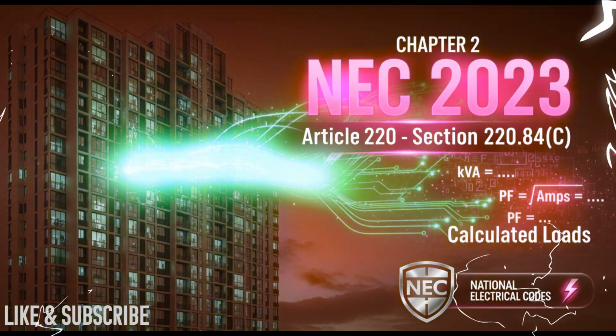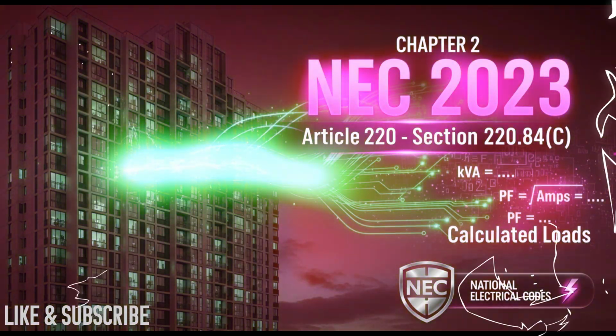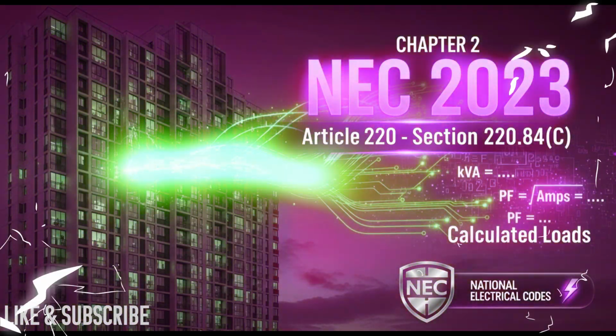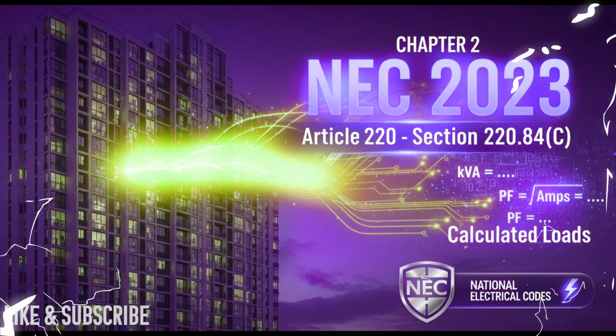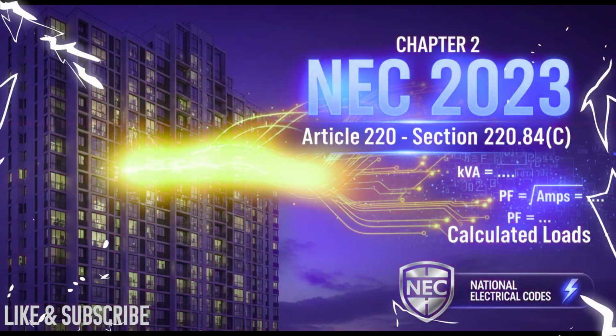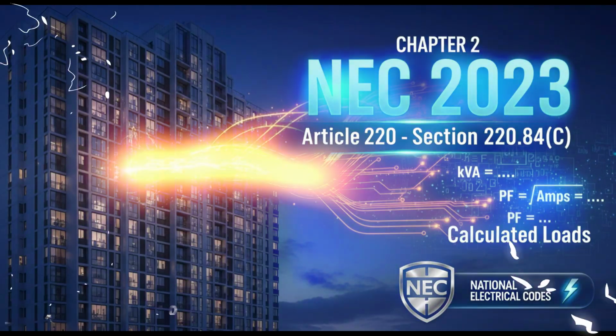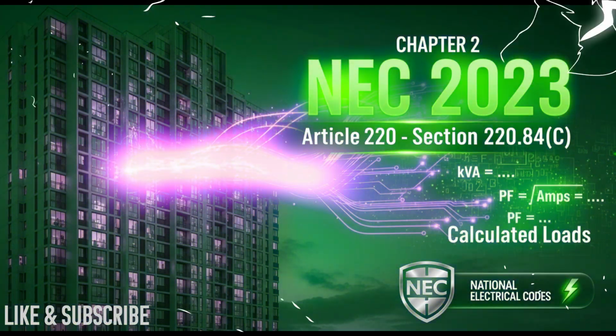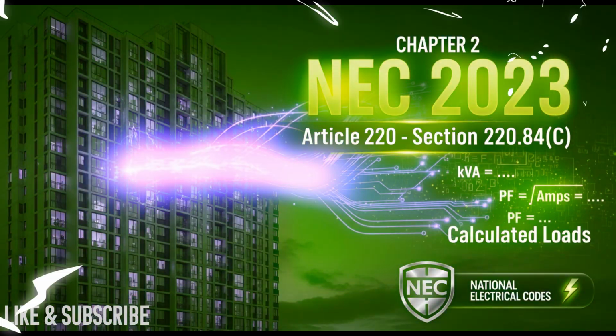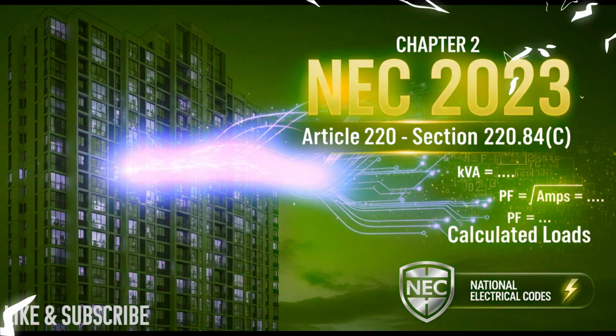But crucially, it also forces you to include the big kitchen players based on their nameplates: ranges, wall-mounted ovens, counter-mounted cooktops. Makes sense. Big loads. Huge. Also, clothes dryers, unless they were already covered by that 1500 VA laundry circuit we just talked about in input 2. If it's a separate higher power dryer connection, its nameplate goes in here. Okay, so you don't double dip on the dryer load. Right. And finally, water heaters. Their nameplate rating must be included here too.